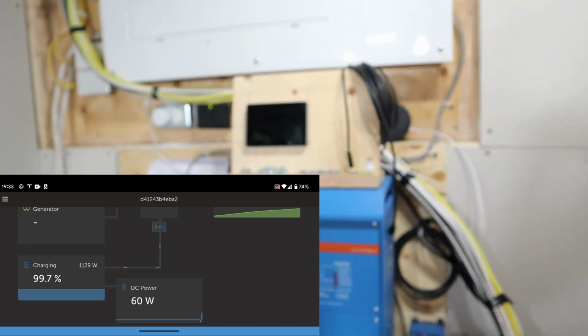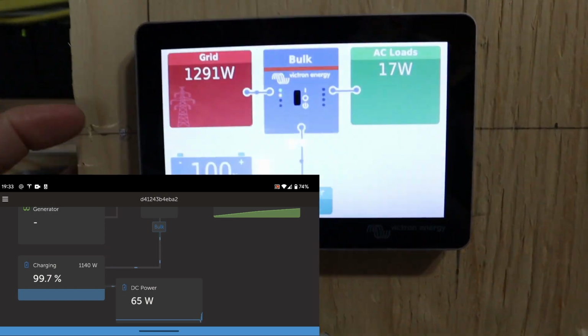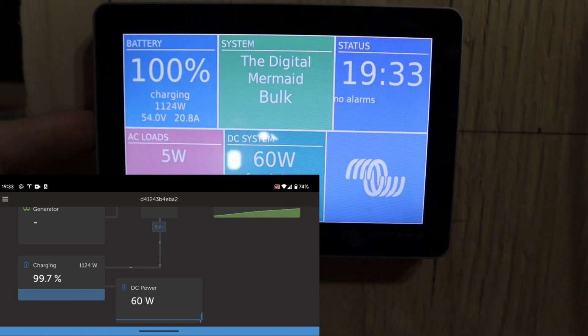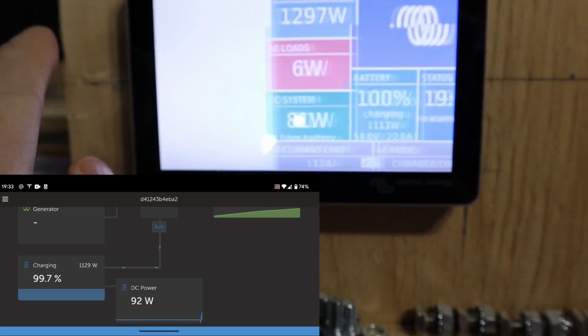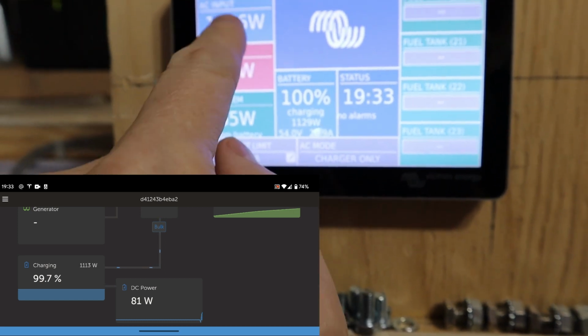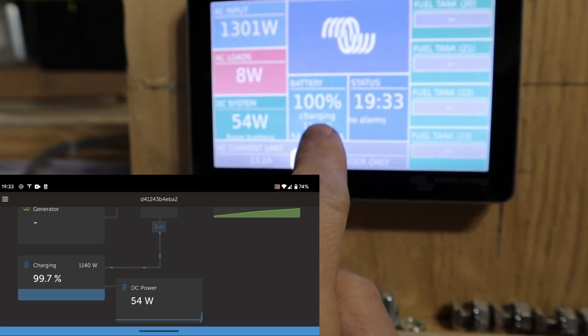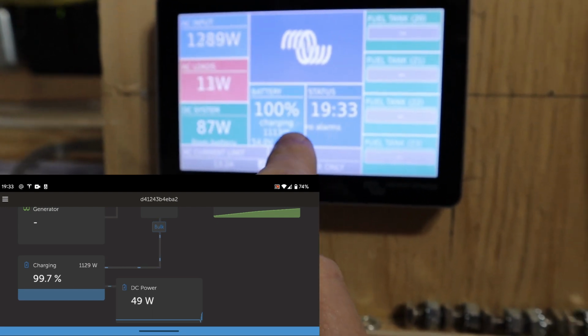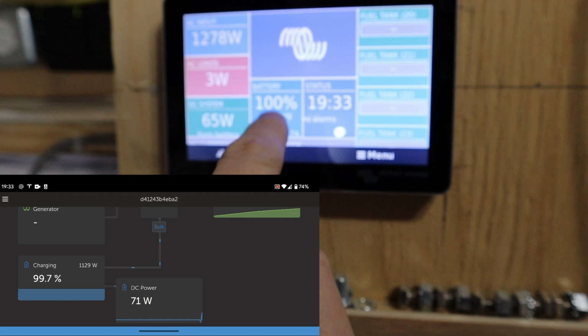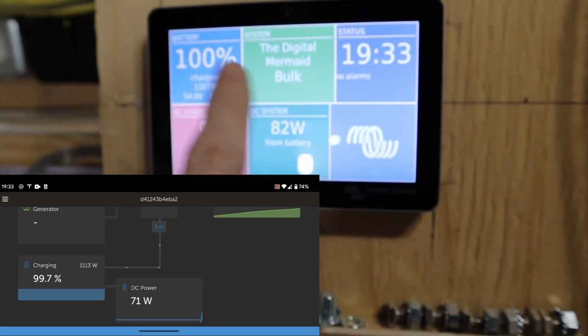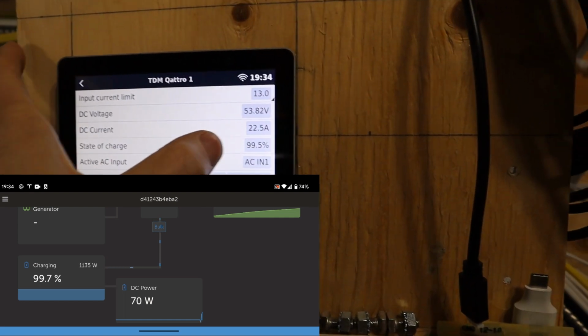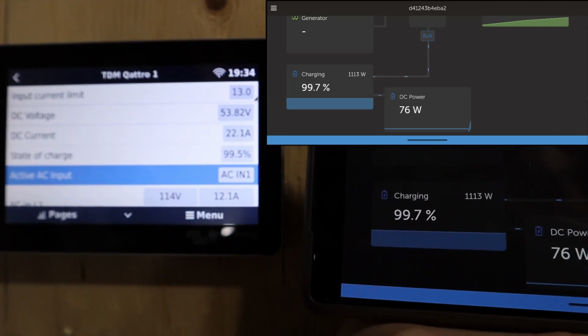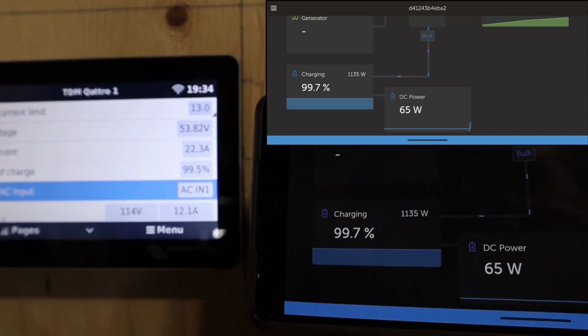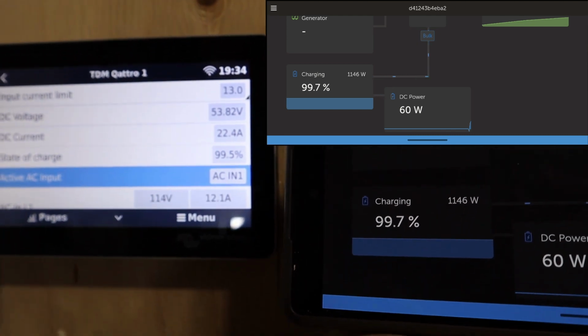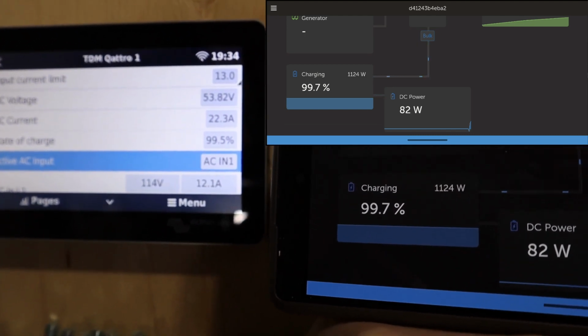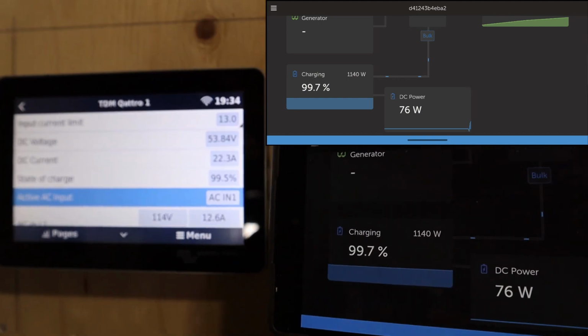I was just complaining about those other screens. Do one of the other screens show higher fidelity? So the app is telling me 99.7. All 3 options on the battery are showing it rounded to 100. There it is, 95 - so the Cerbo GX is showing 99.5, and the app is showing 99.7. I mean, it's a small difference, but why is there a difference? They should be pulling from the same source of data.